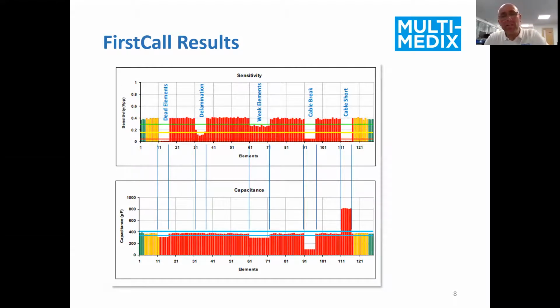Moving along, if all of our capacitance is working correctly, we know we've got a good circuit. However, we've not got acoustic performance due to delamination, but we have got a little bit of performance. That means something's gone wrong in the layers of the array, usually the lens material coming away from the matching layer, and that's stopping acoustic performance. If we've got a drop in performance and a small drop in capacitance, what we've got is a degradation of the individual piezoelectric elements, and that really means what we call weak elements. They're creating some kind of acoustic performance, but not as intended, and maybe affecting the image.